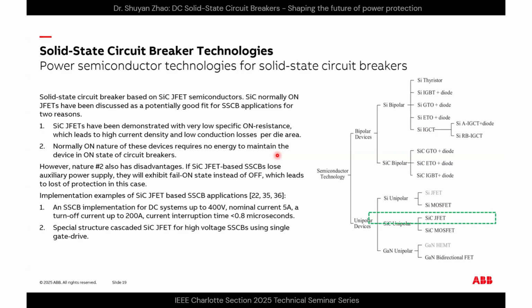That's actually a very energy efficient solution if it just passively conducts for a circuit breaker, because as you know, for a circuit breaker it's really used for interruption -- most of its life cycle is in the on-state. However, this nature also has disadvantages: if a SiC JFET-based solid breaker loses auxiliary power supply, it will exhibit a fail-on or always-on state instead of off. It will lose the capability of turning off, which leads to a loss of protection capability -- if it loses auxiliary power, it loses the function of a circuit breaker.